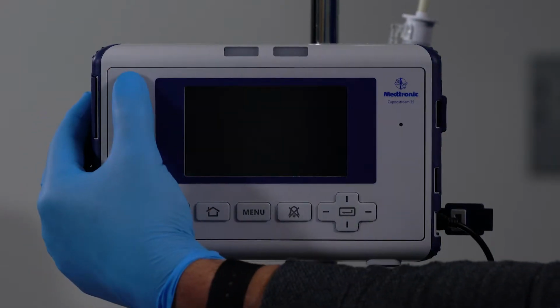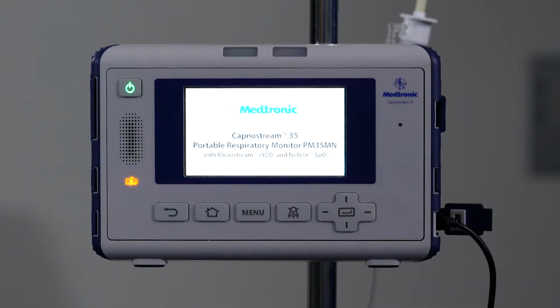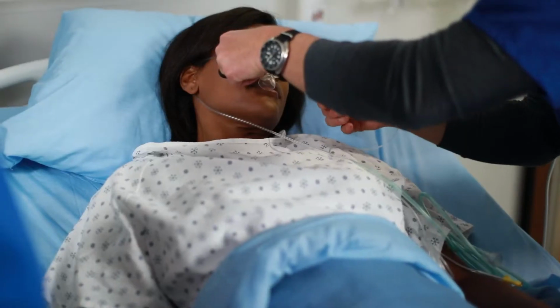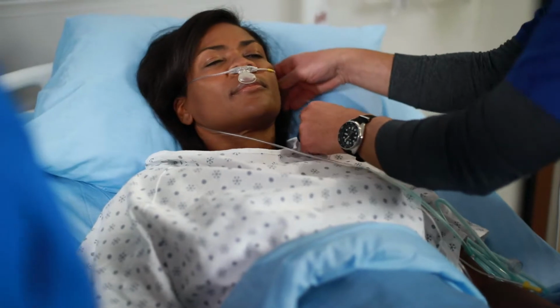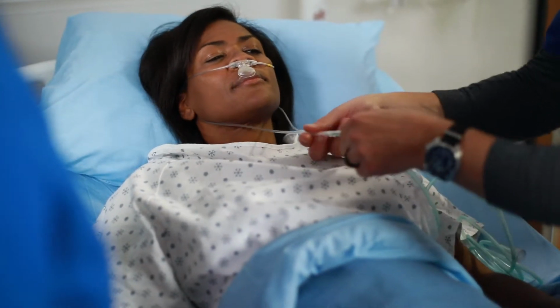To turn it on, simply press the button and you're up and running. No need for calibration. Let's take a moment to see how to properly attach the appropriate filter line sampling line to the patient. The sampling line has a built-in hydrophobic filter and quick connect, a quick seal connector. It samples exhaled carbon dioxide from both the nose and mouth.